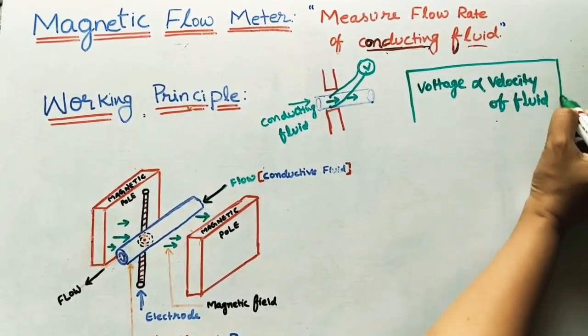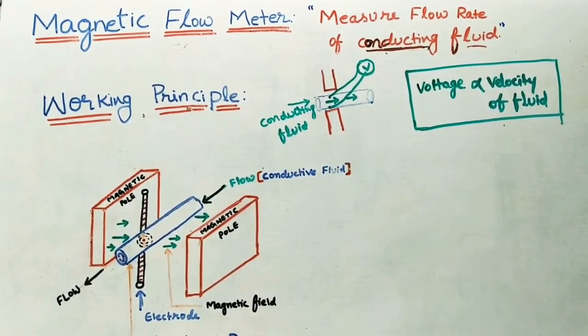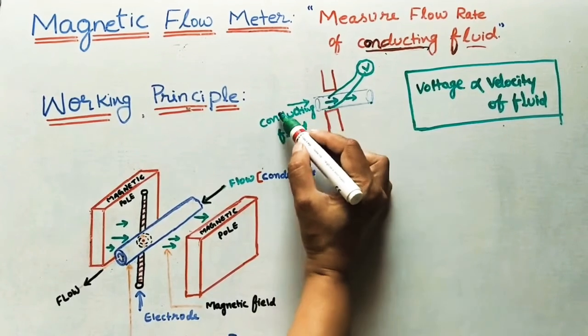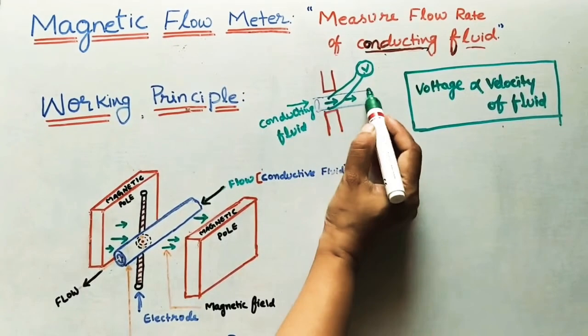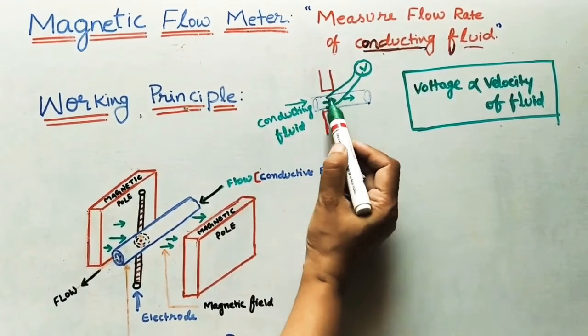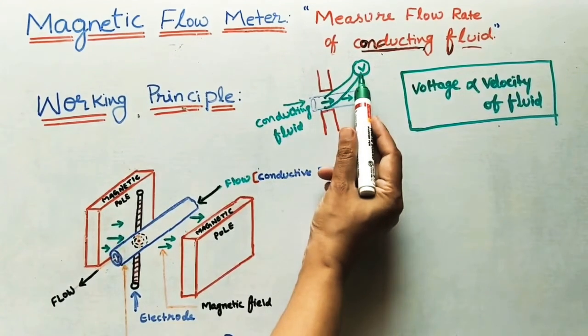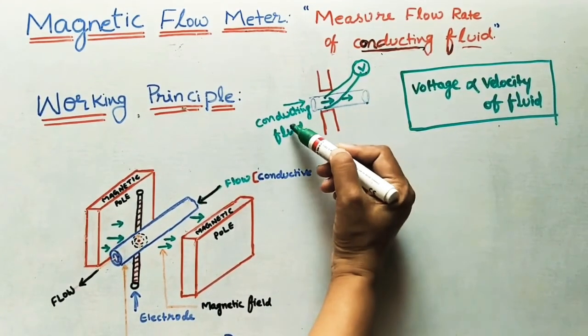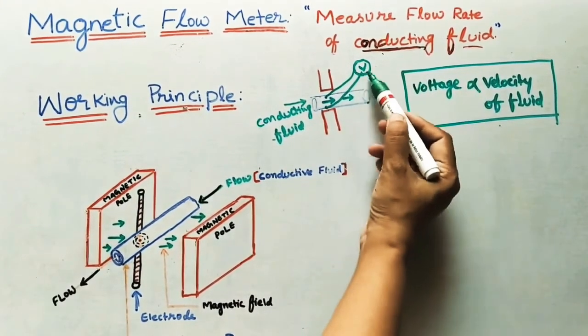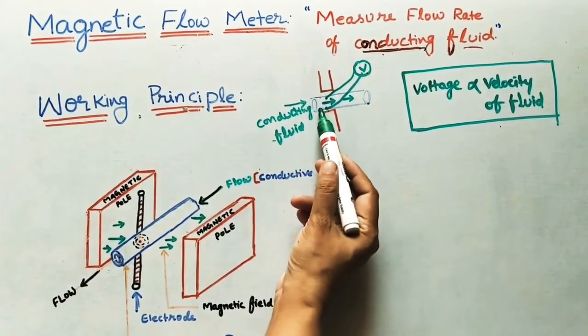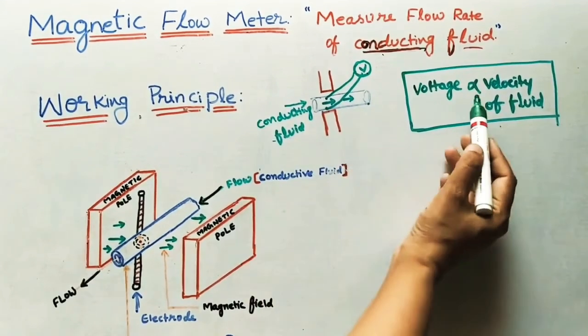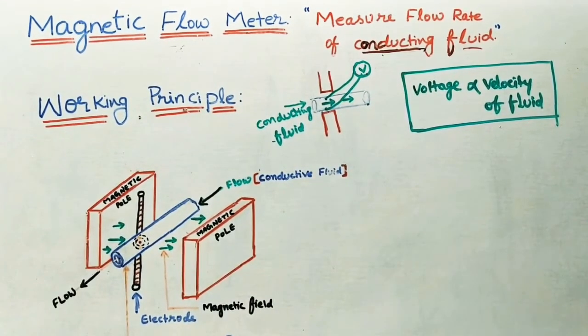This is the working principle of this flow meter. We take the magnets, generate the magnetic field, and send the conducting fluid through a non-conducting pipe. Whenever this conducting fluid cuts the magnetic field, voltage will generate, and this voltage gives the velocity of the conducting fluid. If velocity is more, the voltage is also more. If it is flowing slowly — less velocity — the voltage is also less. The voltage is proportional to the velocity of the conducting fluid.